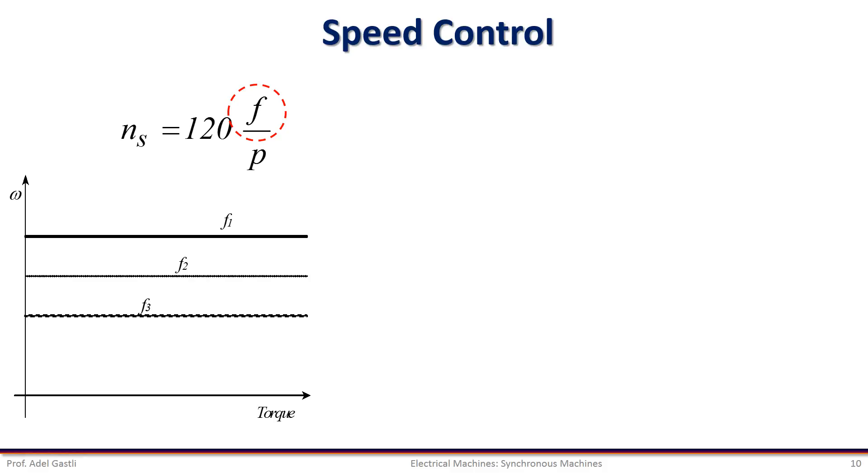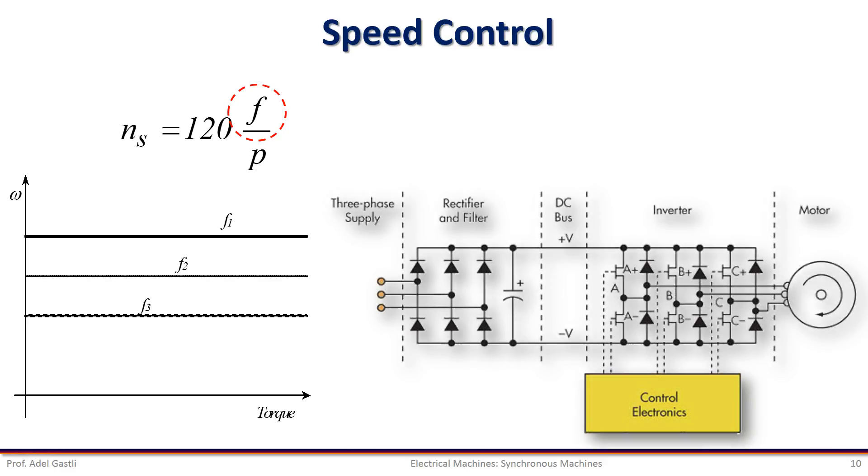Note that, unlike the speed of induction machines, the speed of synchronous machines does not change with the torque. Frequency control can be achieved by power electronics converters, as shown in this example.